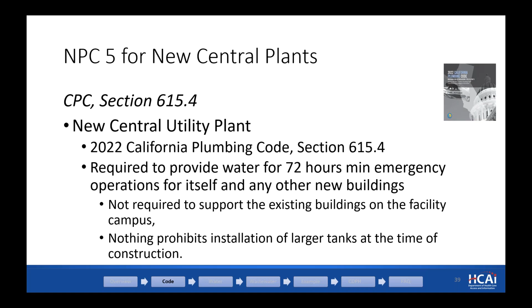So for example, a new central plant has water-based chillers installed. They are serving the new central plant itself and one new building on the campus. The existing chiller for the existing building on the campus can remain as it is. So to meet the NPC 5 requirement, there should be water provided to meet the requirements of the two new chillers that are serving the new central plant and the new building on the campus. But you're not required to provide water for the third chiller at this time, which is serving the existing building. But again, that's something that needs to be calculated and provided for the 2030 deadline and the end of this year kind of timeline for preparing the evaluation report.